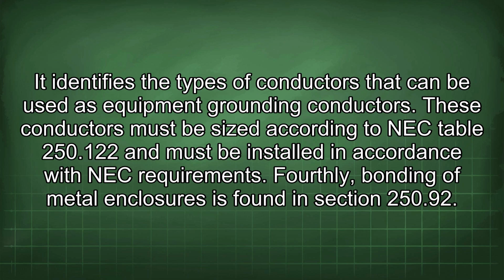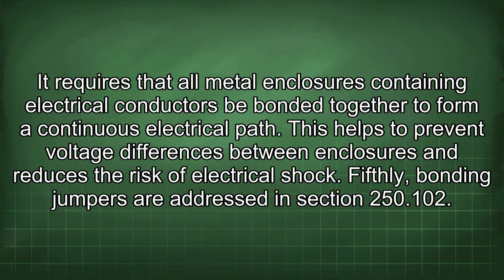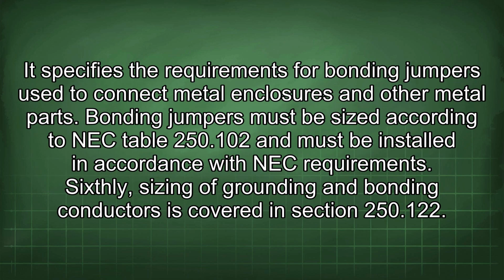Fourthly, bonding of metal enclosures is found in Section 250.92. It requires that all metal enclosures containing electrical conductors be bonded together to form a continuous electrical path. This helps to prevent voltage differences between enclosures and reduces the risk of electrical shock. Fifthly, bonding jumpers are addressed in Section 250.102. It specifies the requirements for bonding jumpers used to connect metal enclosures and other metal parts. Bonding jumpers must be sized according to NEC Table 250.102 and must be installed in accordance with NEC requirements.